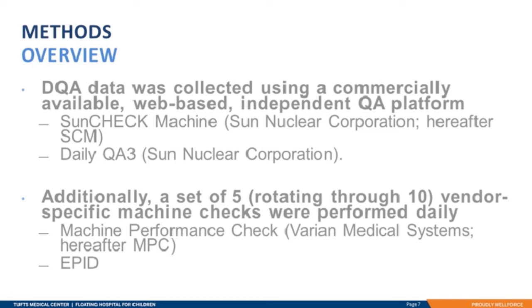With our infrastructure change, we switched to a Sun Nuclear QA platform, which included a SunCHECK machine with the Daily QA3 phantom for daily QA. Additionally, we now had Machine Performance Check available on our TrueBeam. Due to the number of new tests, the new system, and the addition of Machine Performance Check, our radiation therapists were initially very concerned about how much extra time daily QA was going to take in order to be ready to treat for the day. As a compromise, we set up a procedure that split the Machine Performance Check tests so that each day 5 of the 10 tests pertinent to our clinic were performed and the tests were alternating days. We will go over in more detail how that can be set up later.